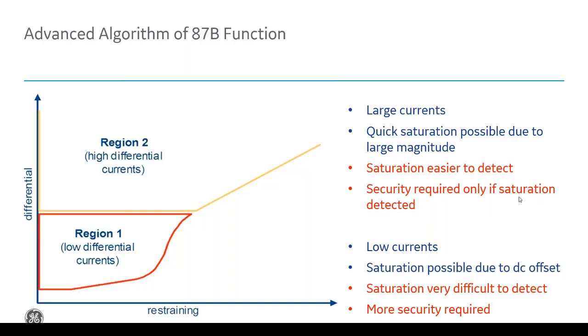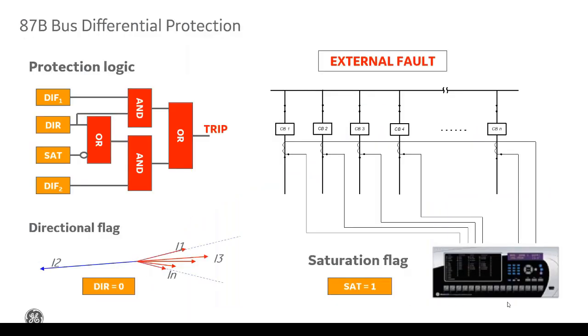We only require CT security if there's a saturation detected, whereas in region 1 of the curve, saturation is very difficult to detect because the fault currents are lower. And due to DC offset, we could have saturation that can be very low. So more security is required in that region of the curve. So what we basically do is we have a directional element. Before the CT saturates, the CT does not saturate right away. There's a finite time before the CT saturates. So we can determine the directions of all of these currents before the CT saturates.